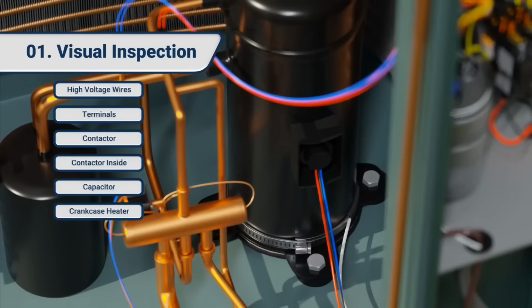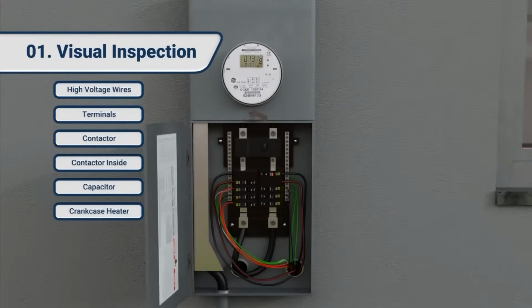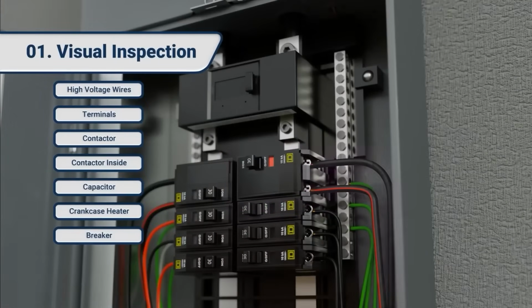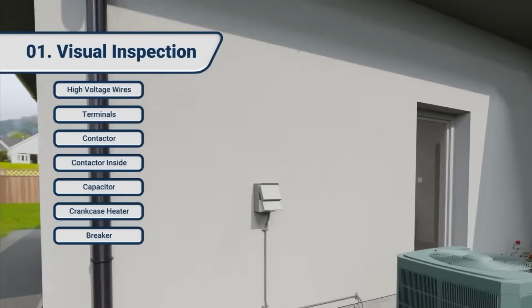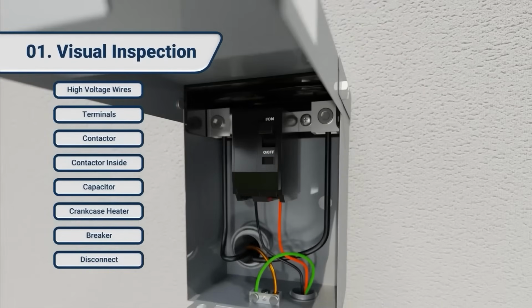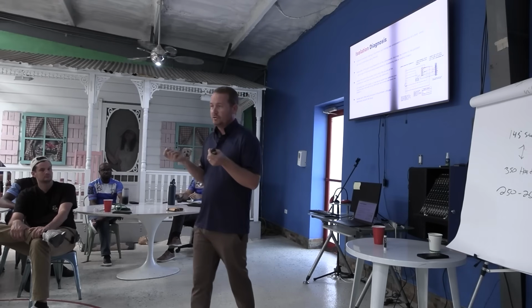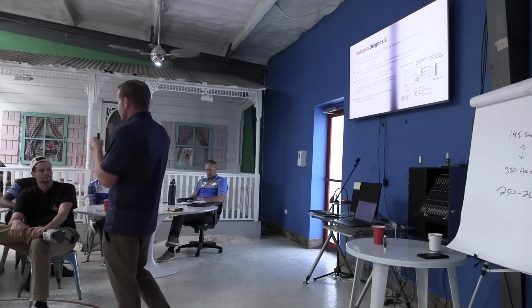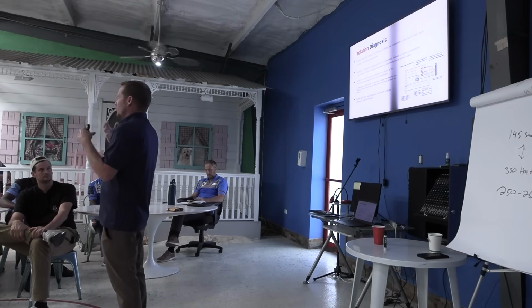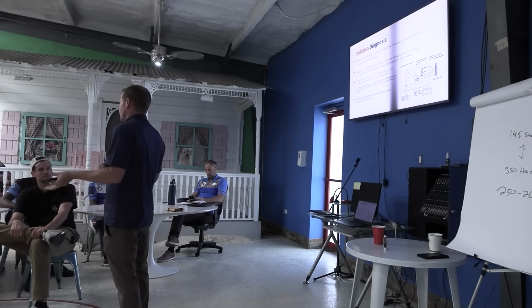I'm going to go in there and look. Is there anything? If it's one of the ones that often have shorted contactors—are you guys still running into the shorted contactor coil issue? In that case you can either eliminate it by disconnecting it and retesting, or you can actually ohm out the coil if you know what you're looking for. But basically you're doing a visual inspection, looking at the most plausible causes before you do anything else.